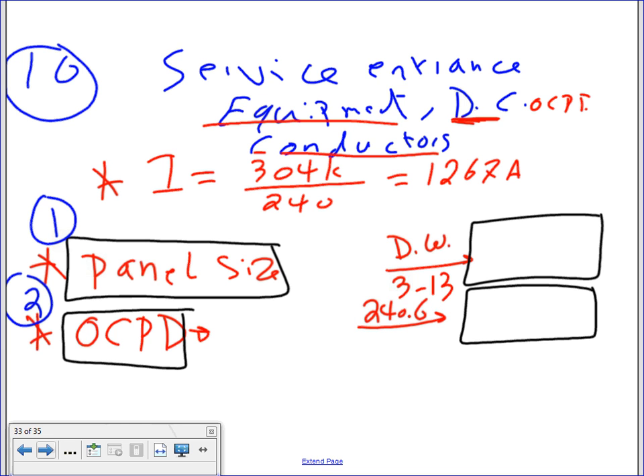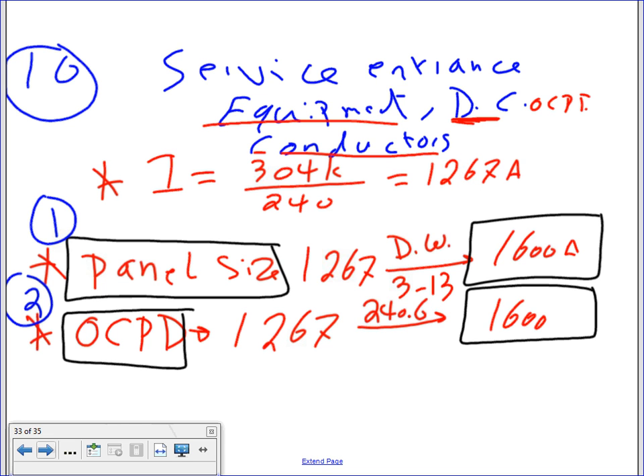Then you take the 1.25. So that's the panel size, 1267 amps. Table 240.6 will get you 1600 amps. 1600 amp panel. And overcurrent protection device, the same thing, guys. 1267, 240.6 gives you a 1600 amp. Huh?